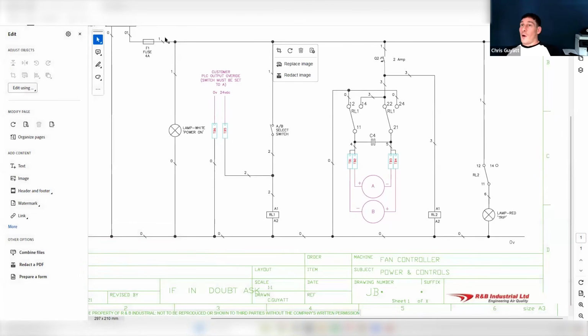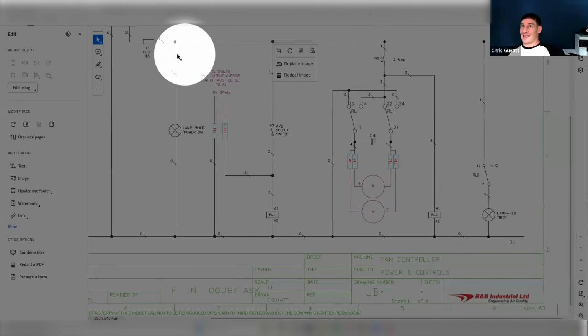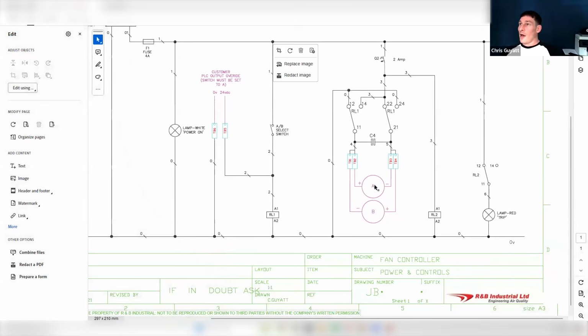So what we've got, again, is 24 volts coming out of the power supply up here, and then it's just going through. What we've got here is just an overload. So basically like an MCB, but it's a thermal overload, specifically designed to protect these dampers here. What we're doing is that if everything's healthy and these haven't tripped out, then that will be closed.